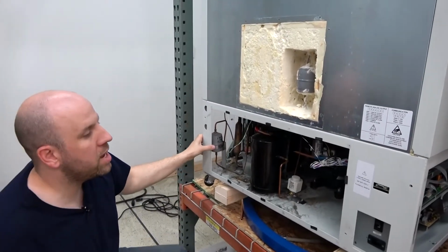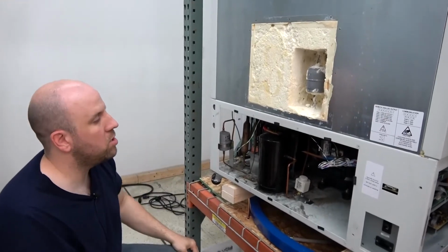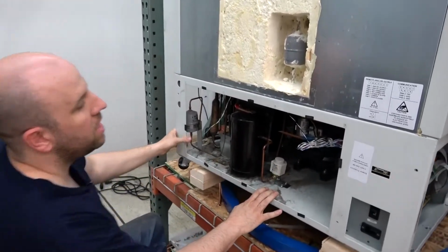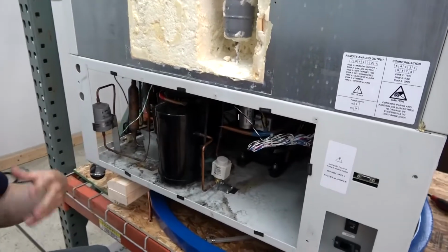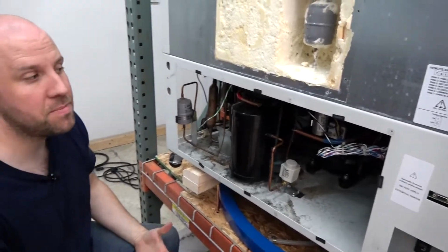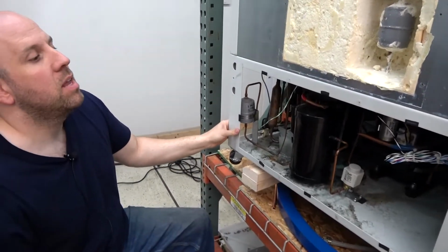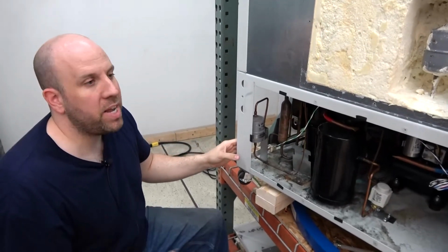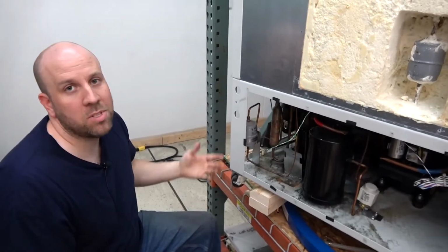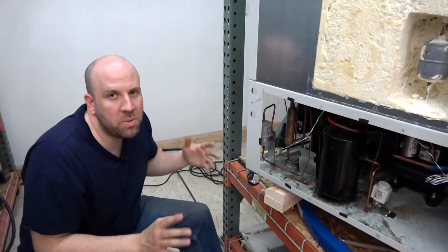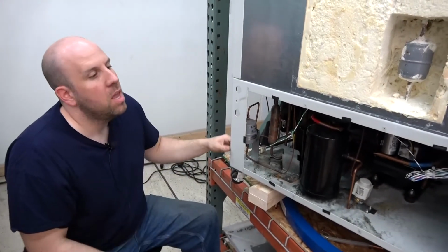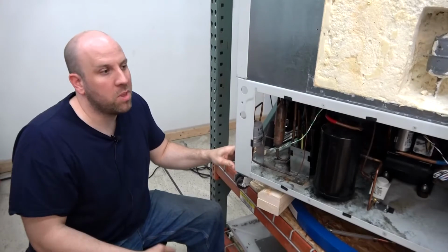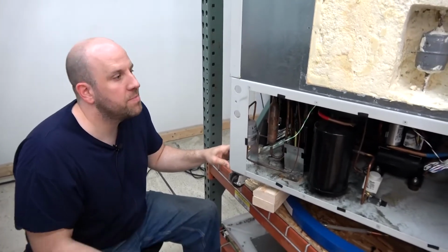So what happens during operation: first stage comes on, this compressor kicks on, it takes the refrigerant in a gas state and compresses it. Depending on the model, a lot of times it's around 150, 160 psi. It changes with temperature. When it's operating normally, sometimes it's lower, in the hundreds.